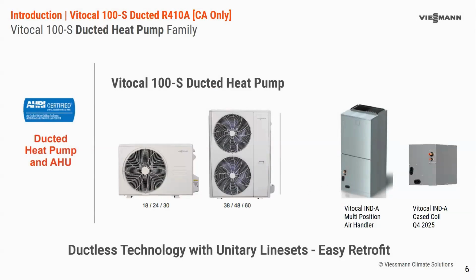So a lot simpler of a lineup compared to the ductless as far as equipment selection. We have an outdoor unit, we have an indoor unit. That hasn't changed. The difference is the application and some of the technology. So we like to say this is like the best of both worlds. It's ductless technology that mates right up to central ducted infrastructure. So the line sets are larger to match what's traditionally in a central ducted system. There's already 24-volt capability built into both the outdoor and the indoor unit, as well as the EEV in the outdoor unit is only in heating, and that allows you to only insulate one of the suction lines.